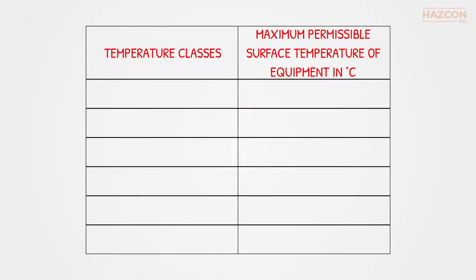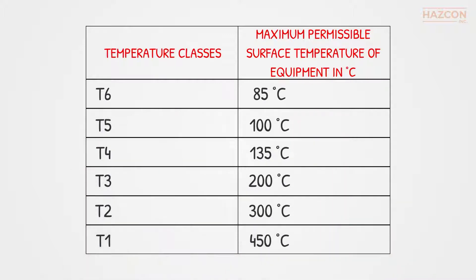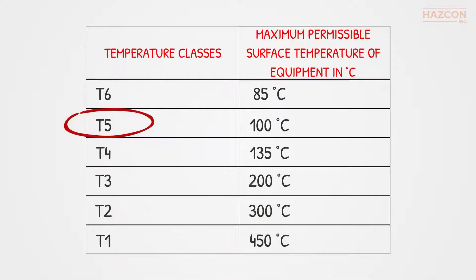There are six main temperature classes named as T6, T5, T4, T3, T2, and T1. What this table means is that a device classified as T5 will never attain a surface temperature higher than 100 degrees Celsius, which can be exposed to explosive atmospheres and cause an explosion.